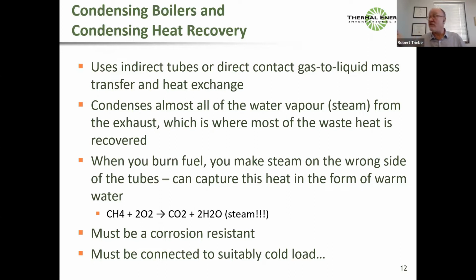Of course, when we burn fuel, we're basically making steam on the wrong side of the tubes, because when you burn fuel, you're burning C's and H's. When you burn C's and H's, you make CO2 and H2O. And if you're making H2O as a combustion product, it means you've got steam in your flue gas. If we can condense the steam out of that flue gas, we make a big energy efficiency impact.